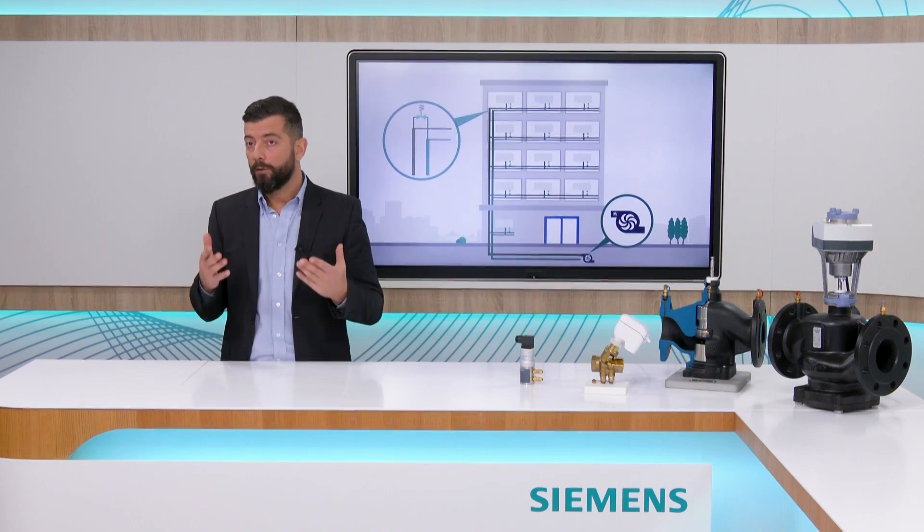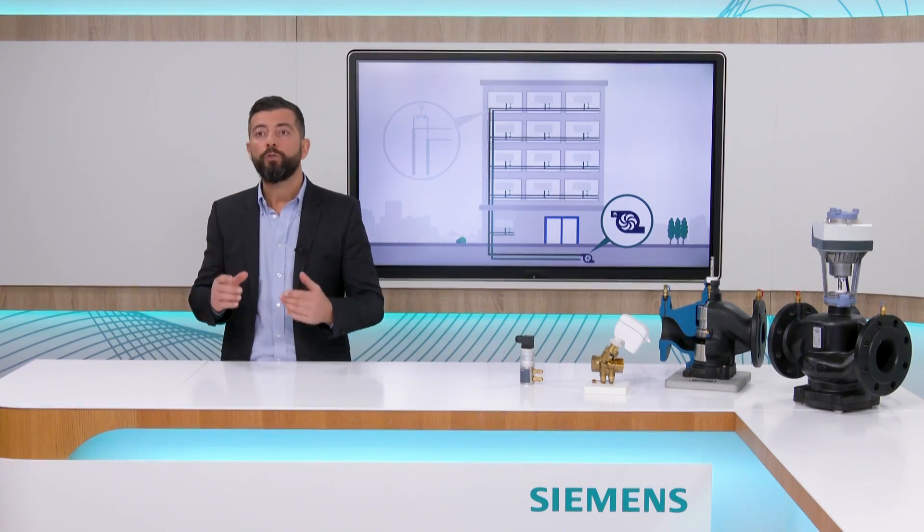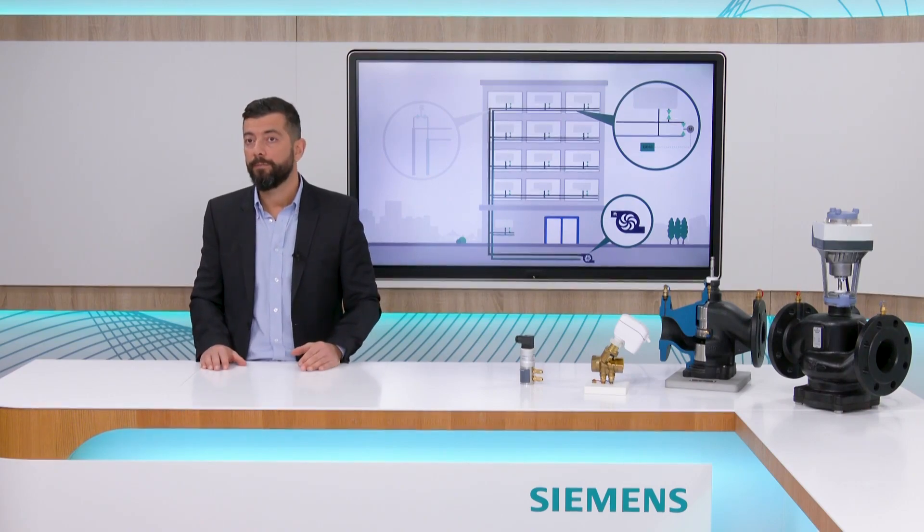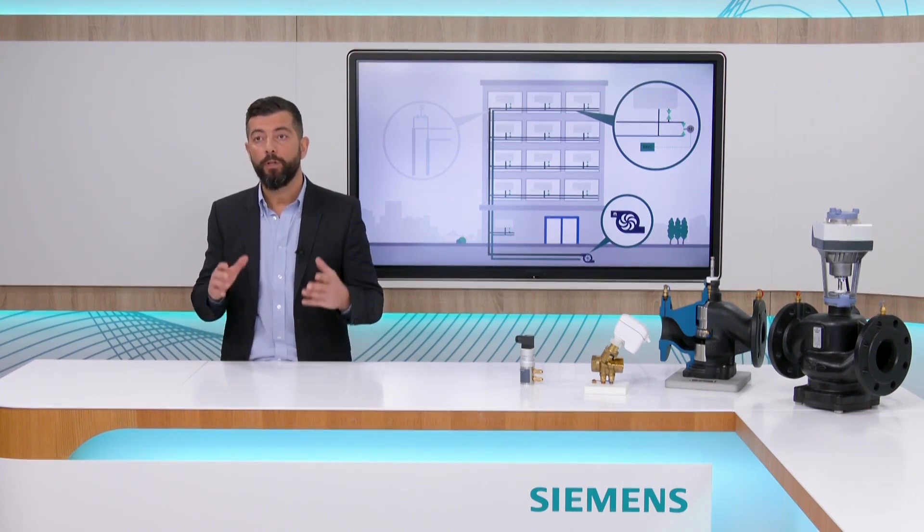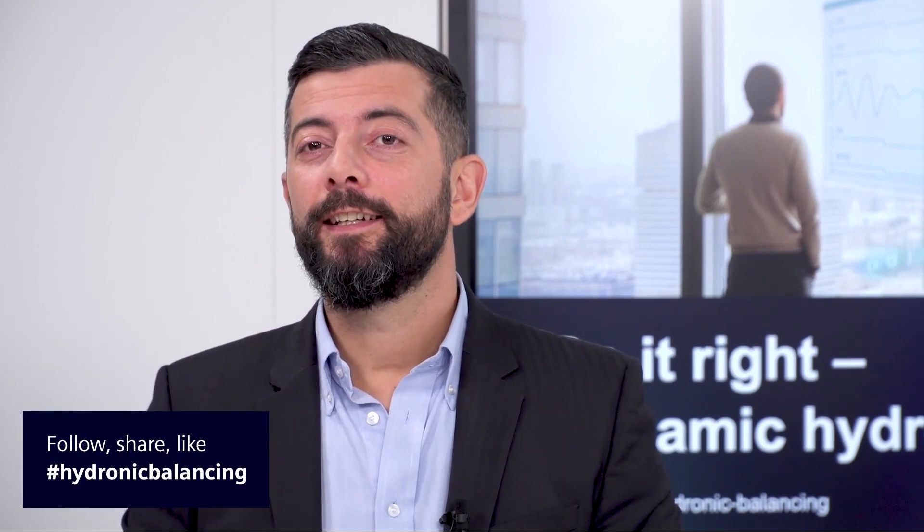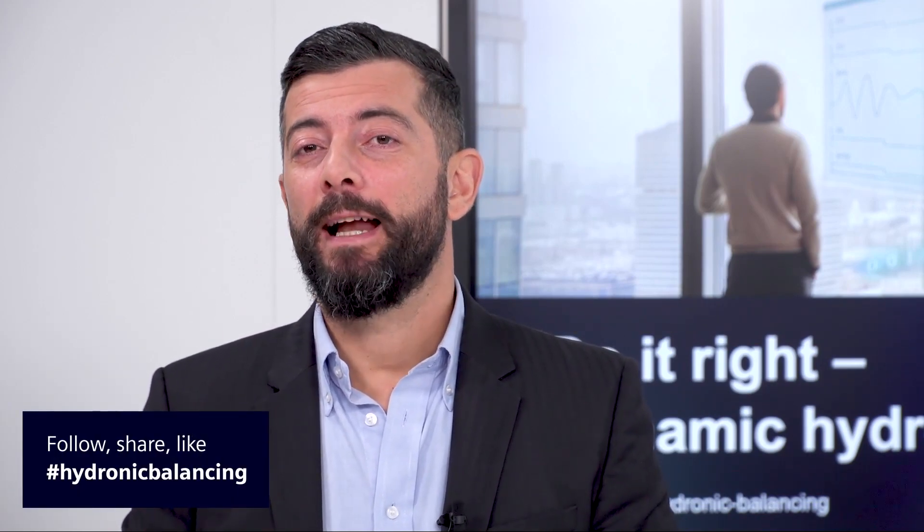The best solution I would like to suggest is to use controlled bypasses, which open only when it's needed and perhaps are even dynamically balanced, to reduce the impact of the recirculating water on the delta T. Thank you for watching. Do it right. Dynamic Hydronic Balancing.